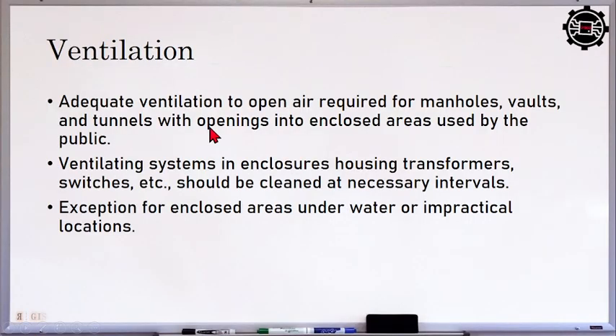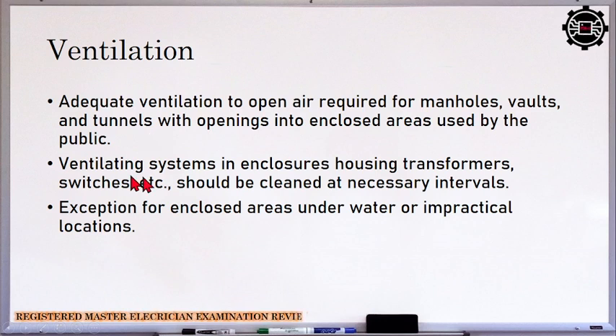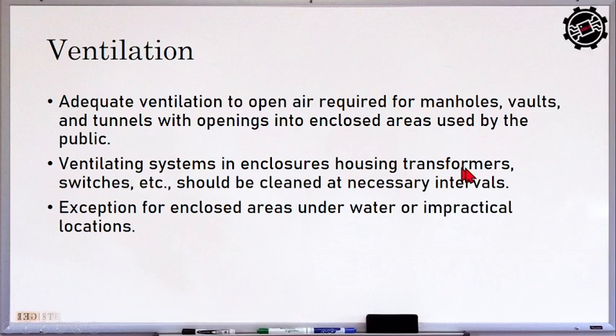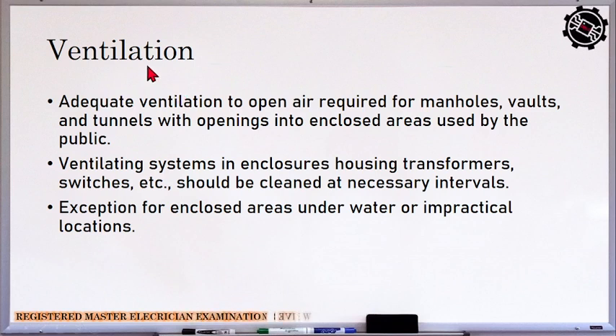Okay, the ventilation. So adequate ventilation to open air is required for manholes, vaults, and tunnels with openings into enclosed areas used by the public. In the ventilating system and enclosure housing transformers and switches, it should be cleaned at necessary intervals. So kasama yung cleaning of the ventilation system of our enclosures, no? Exception for enclosed areas underwater or impractical locations. For example, our cables, or our underground supply system, is going through a body of water, so it is impractical to maintain our ventilation. Kasi tubig na sila ng tubig na yon.